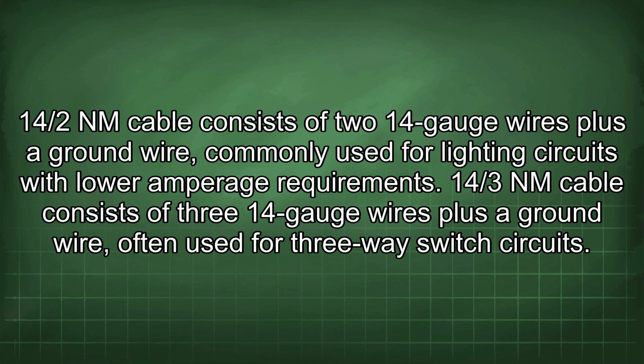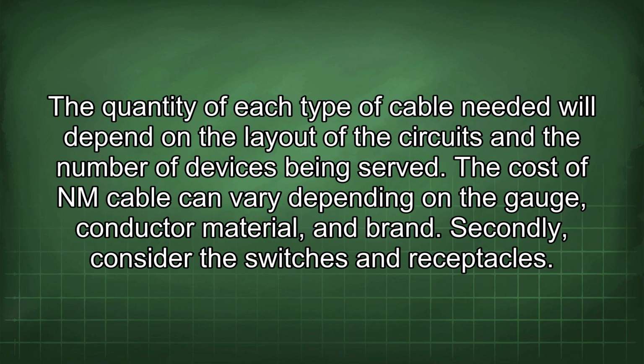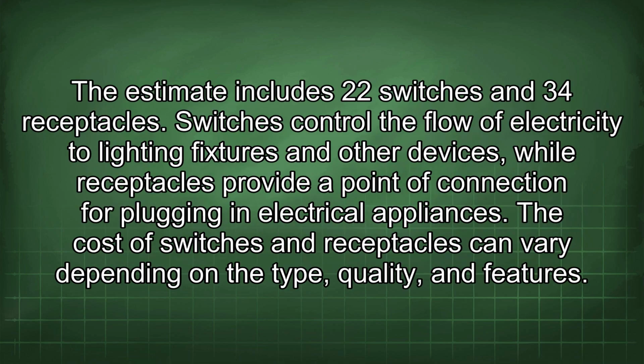14/3 NM cable consists of three 14-gauge wires plus a ground wire, often used for three-way switch circuits. The quantity of each type of cable needed will depend on the layout of the circuits and the number of devices being served. The cost of NM cable can vary depending on the gauge, conductor material, and brand. Secondly, consider the switches and receptacles. The estimate includes 22 switches and 34 receptacles. Switches control the flow of electricity to lighting fixtures and other devices, while receptacles provide a point of connection for plugging in electrical appliances. The cost of switches and receptacles can vary depending on the type, quality, and features.